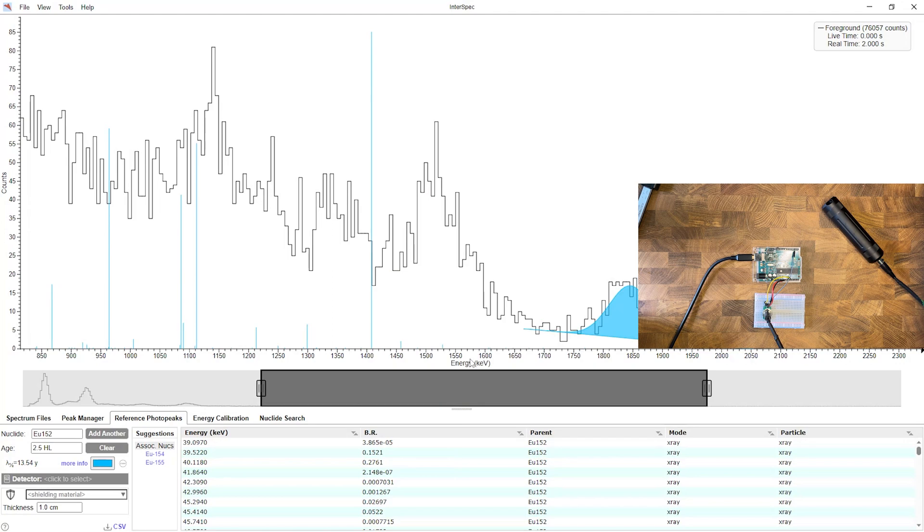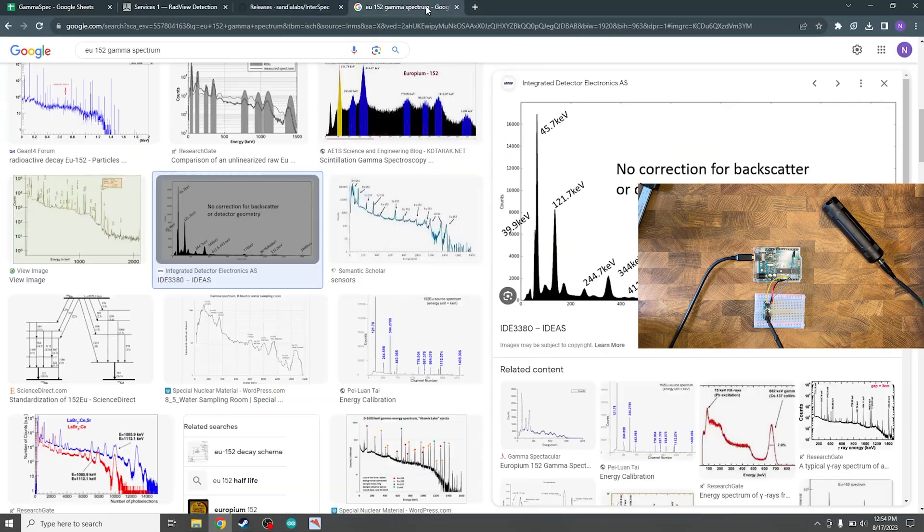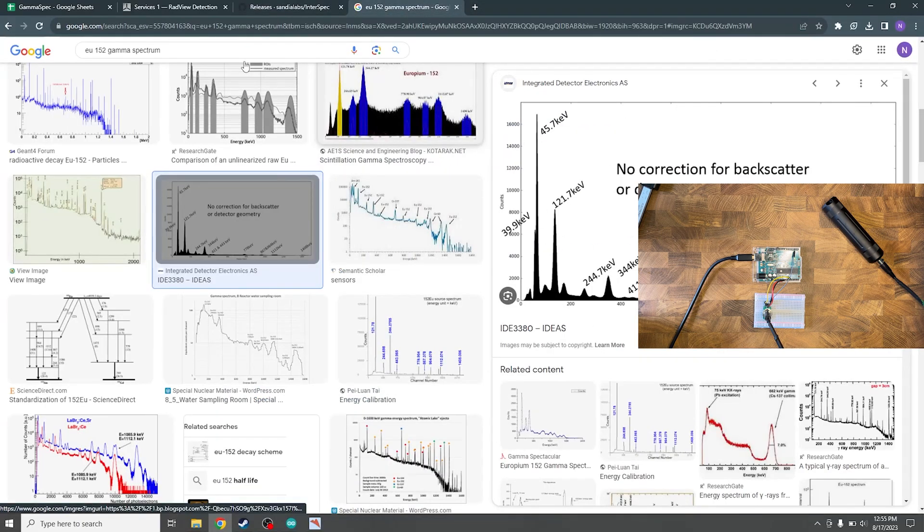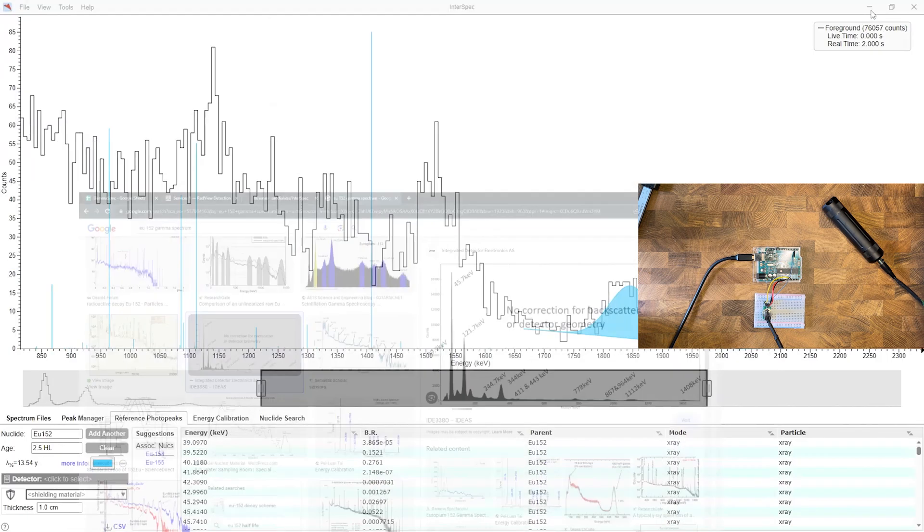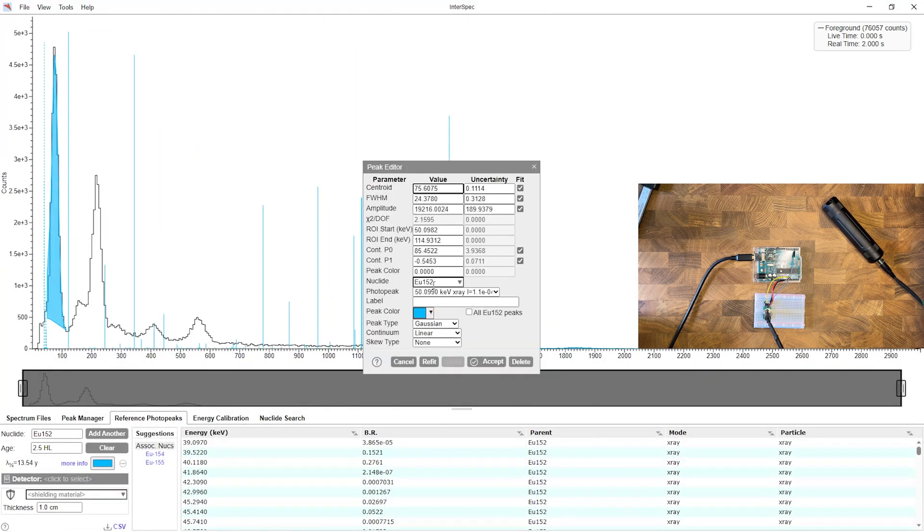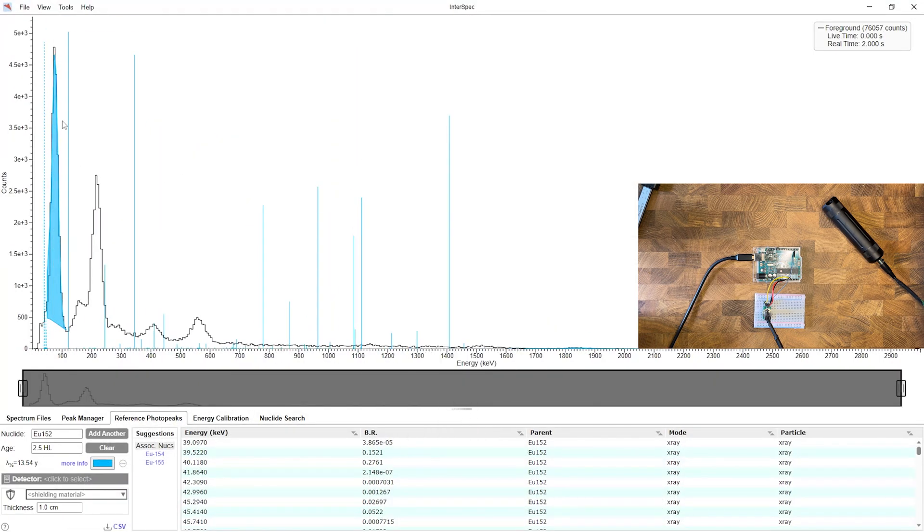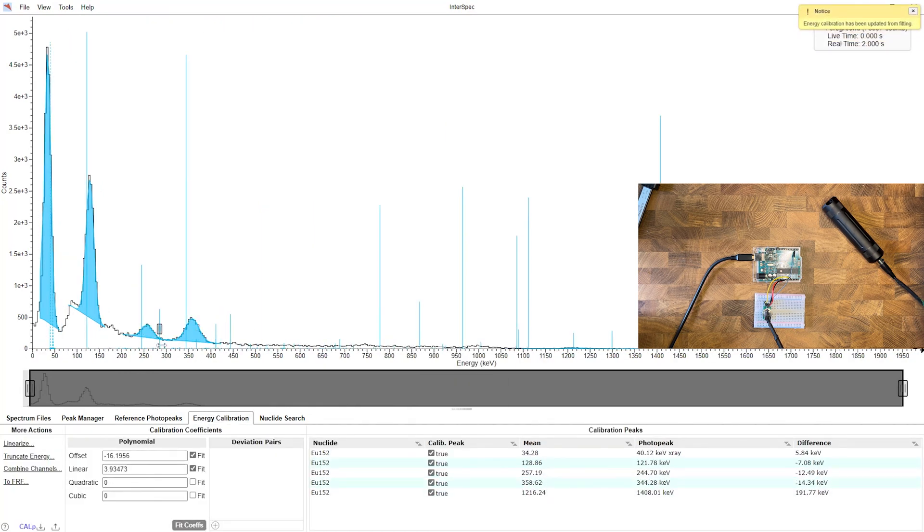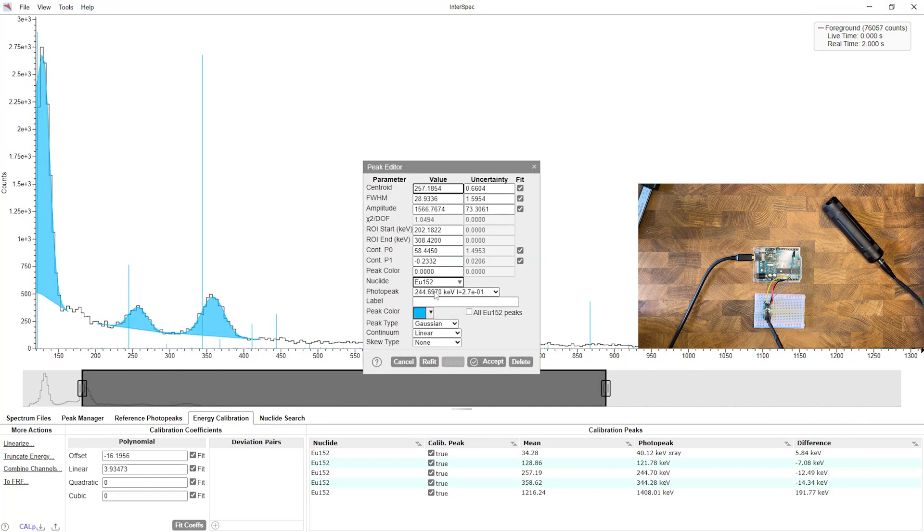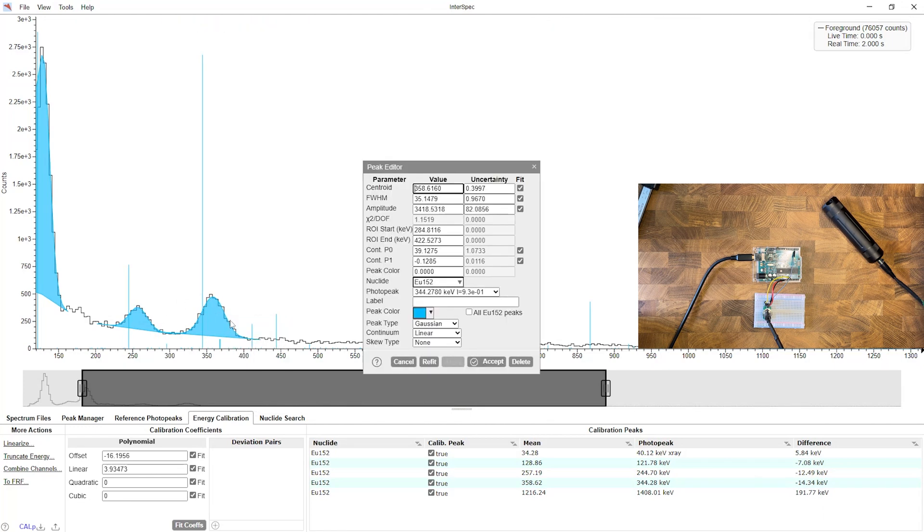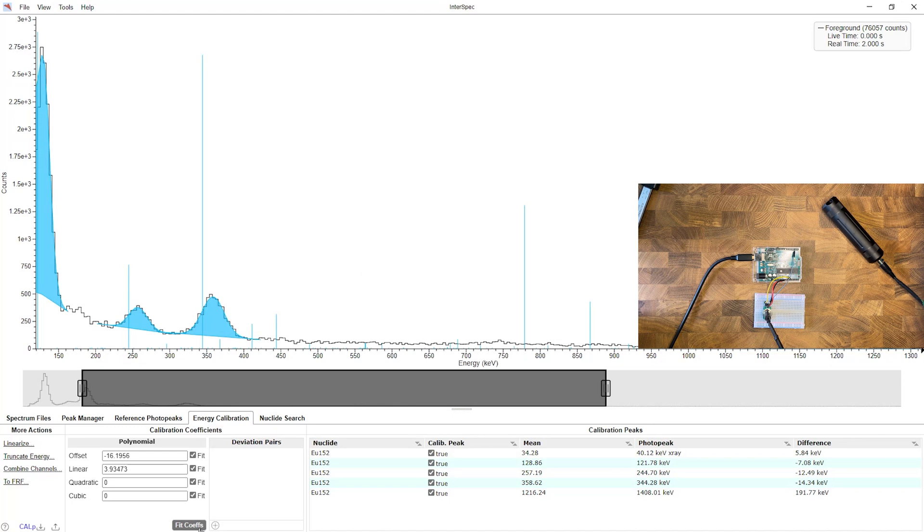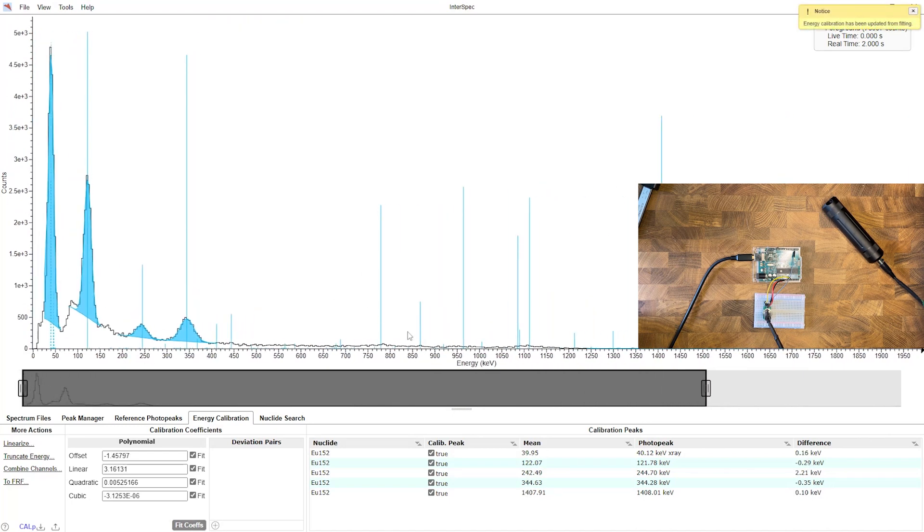Another quick tip, if you're looking for spectrums, you can also just Google your isotope and then gamma spectrum at the end of it and kind of see examples. So it'll help you line up your spectrum. Once you start getting close, you can hit fit coefficients. So you can see that one is correct and I'm going to make sure this one's correct at 344. So we can hit fit again, get a better fit.